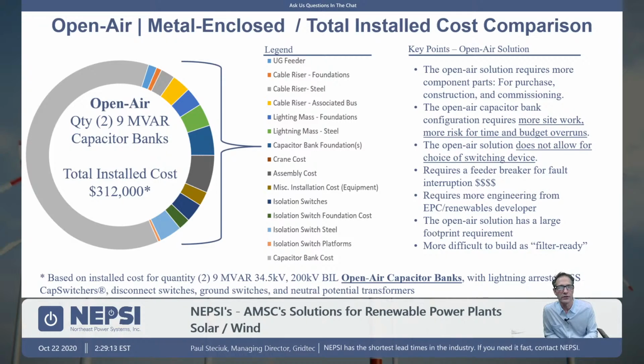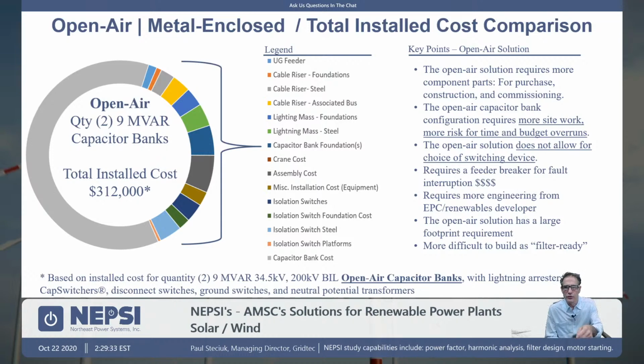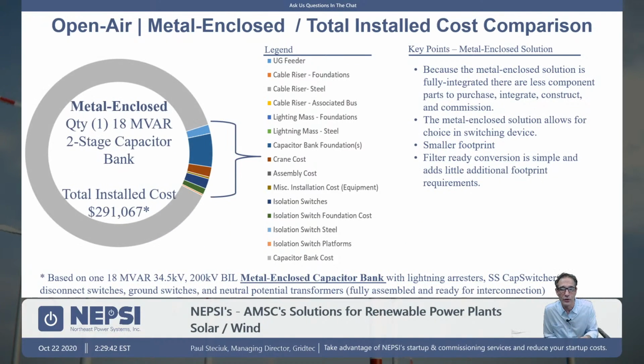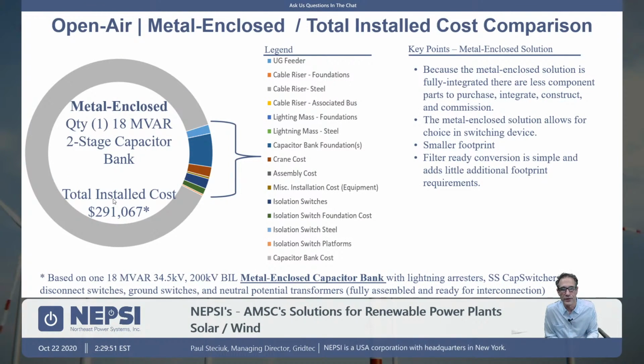So this company was in the process of trying to evaluate, should they go with open air or should they go with metal enclosed? They factored in all the costs associated with the two 9 megavar cap banks as an open air solution, and they came up with a total installed cost of $312,000. So it includes the equipment and component cost as well as the site and commissioning costs, so $312,000. When you compare that to the metal enclosed option, this same EPC came up with a total installed cost of $291,000. So a lower cost, a cost savings, and a lot more simplicity. And that's really the key here, more simplicity.